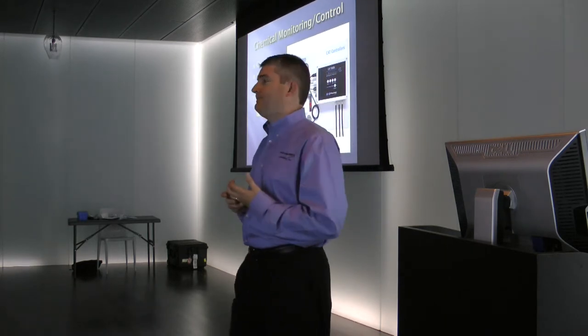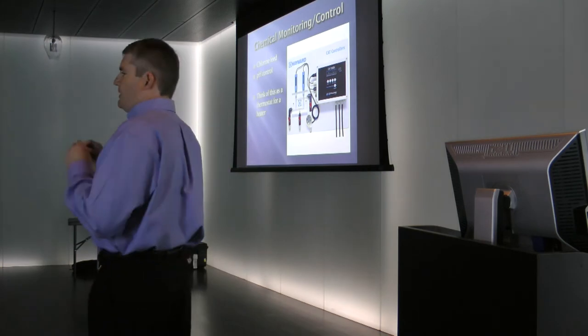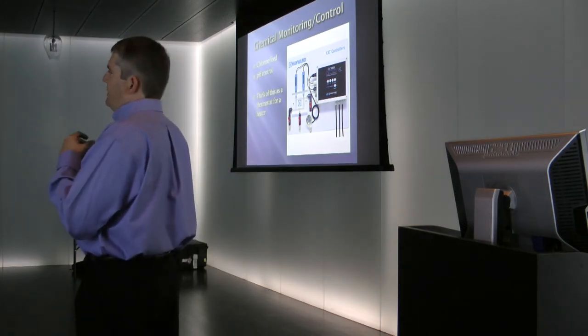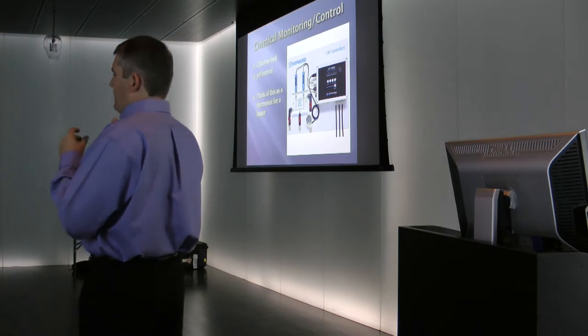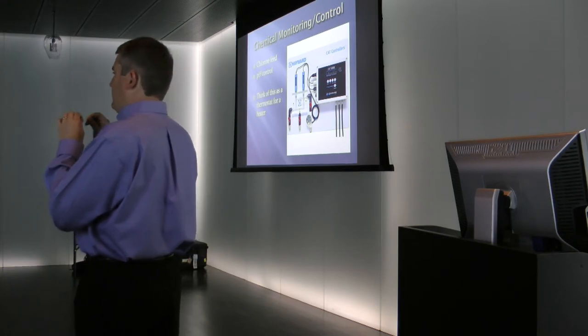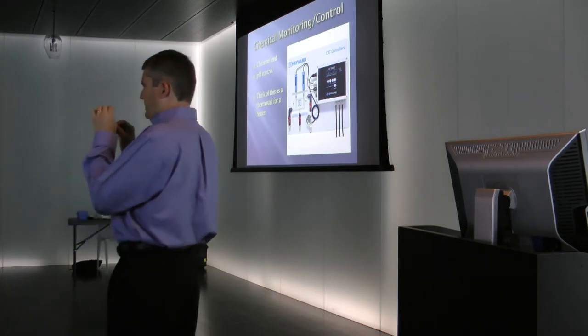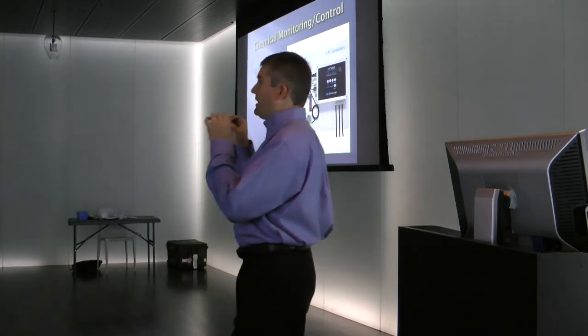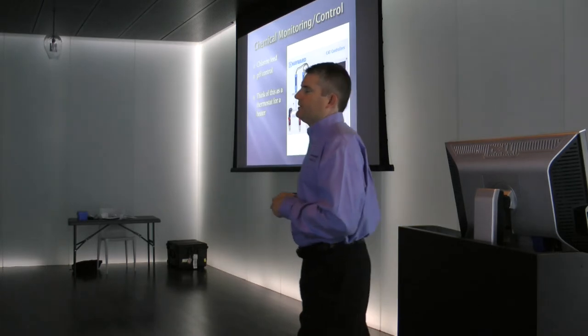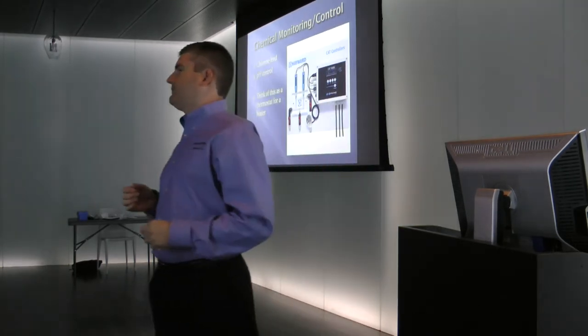Yeah, there's actually a little pore. There's a chemical in there. Think of it like a battery; that's really the best way to describe it. There's a reference chemical that has to sort of leak out, and the probe is comparing that reference to the actual water chemistry to determine what the chemical range is. So eventually the probe runs out of the KCl.